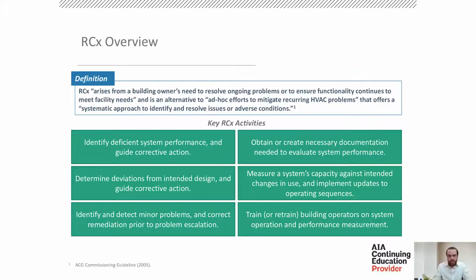Also, in all likelihood, the documentation that existed from the original design is probably lost or obsolete. So going into an operating system, determining how it's operating, and defining that as well is something the retro-commissioning agent needs to be able to do. Documentation is a key thing commissioning agents need to do, and it's no different here — you're just often starting with a blank sheet of paper.